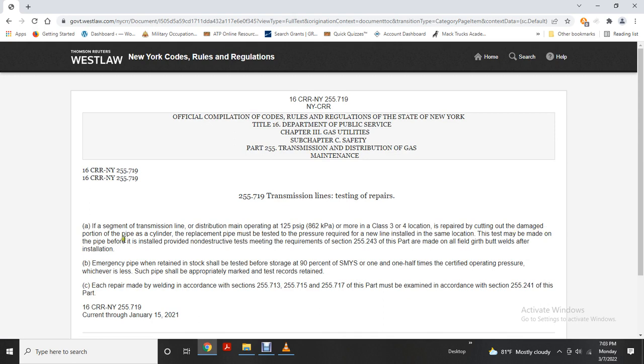Testing may be done on the pipe before it is installed, provided that the testing meets the requirements of section 255.243 of this part. The field girth welds made after installation of the test pipe must be nondestructively tested. The test pressure must be at least 90 percent of the specified minimum yield strength or 1.5 times the maximum operating pressure, whichever is less. The pipe must be properly marked and the test records retained for each repair made. Welds must be made in accordance with 255.713, 255.715 and 255.717, and examined in accordance with section 255.241 of this part.